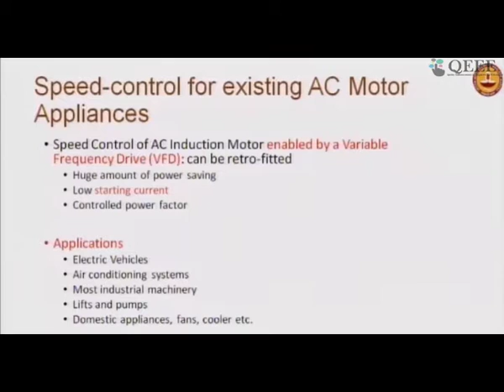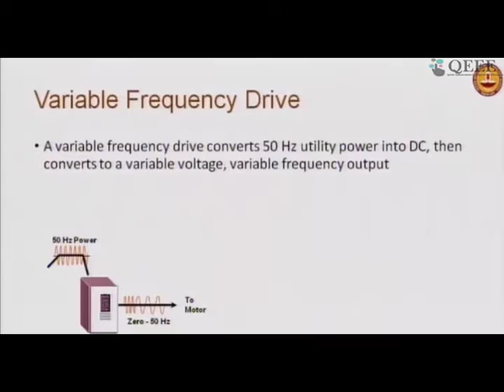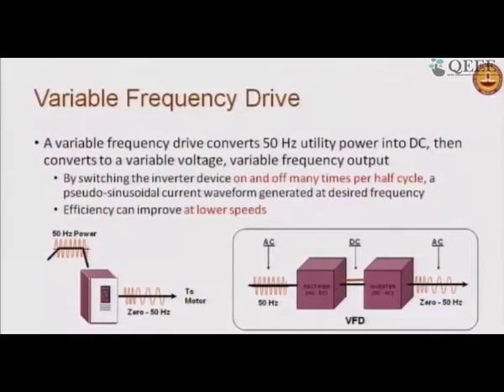So the application is: you use AC induction motors wherever DC motors aren't available—electric vehicles, air conditioning systems, most industrial machinery, lifts and pumps. In fact, recent lifts and pumps all have variable frequency drives, as do domestic appliances like fans and coolers. This drive is powered by DC: AC is converted to DC, then converted into a variable frequency, switching the inverter device on and off many times per cycle to generate a pseudo sinusoidal current waveform at the desired frequency.